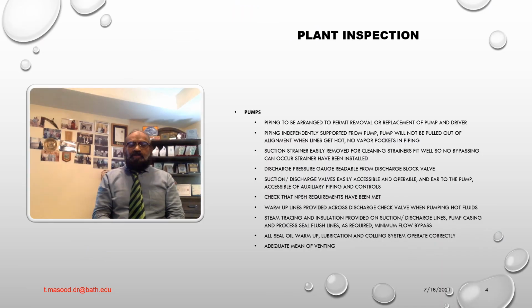Okay, plant inspection pumps. So the following items should be checked for all pumps against P&IDs and vendor drawings. Number 1, piping to be arranged to permit a removal or replacement of pump and driver. Number 2, piping independently supported from pump. Pump will not be pulled out of alignment when lines get hot. No vapor pocket in the piping. Number 3, suction strainers easily removed for cleaning. Strainers fit well so no bypassing can occur.